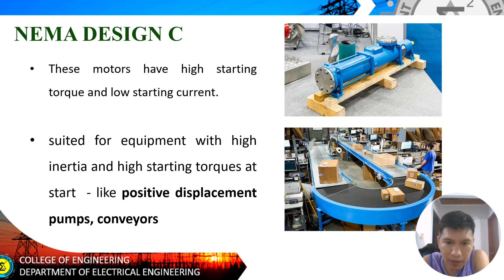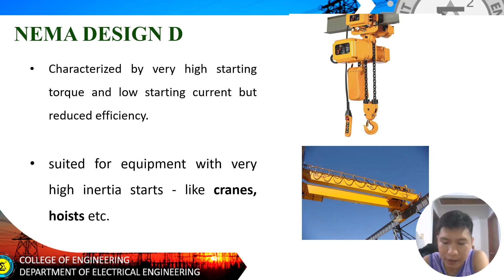NEMA Type Design D is characterized by very high starting torque and low starting current but reduced efficiency. It is suited for equipment with very high inertia starts like cranes, hoists, and other similar things. So, yan yung ginagamit nila sa mga cranes na yan. Okay, NEMA Design D.